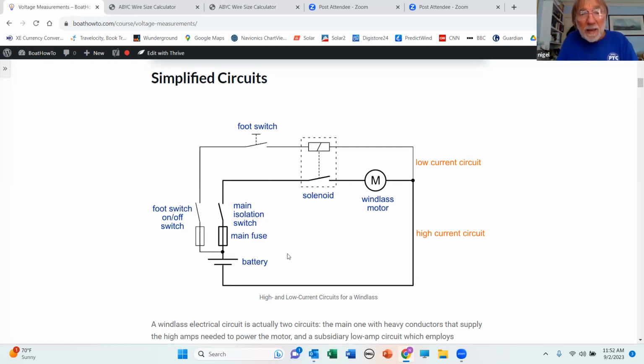Well, now, let's open this switch, but this one, we'll keep this one closed. So we've now moved the positive battery post as far as here, and here it stopped because the switch is open. The negative, we've moved the negative battery post up to the load, and here's the bit that I know a lot of you have trouble with. Most of the loads on our boat, when they're not turned on, remember we've got the switch open, look like a piece of wire to a meter in its volts mode. So at this point, we've now moved the negative battery post through the load, whatever it happens to be, to here. So we've got positive here and negative here, and if we put the voltmeter across the open switch, we should read battery voltage.